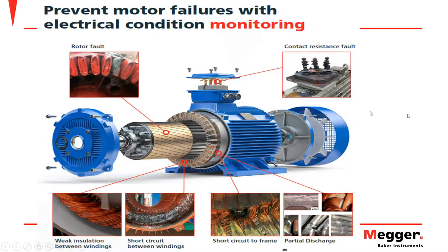Now, to prevent electrical failures, you can see here are some real issues that have led to motor failures. Some are just high resistance joints. Some are total burnouts. Some are just fusing to ground. Some are just a single phase that's burnt out, as opposed to a total burnout, for example. And the very left small window at the bottom there shows a little bit of arcing between some turns. Now, that is how these issues start: a little bit of arcing during startup. But then over a period of time of those startups, because of the AC condition of the startup current being positive, negative, it kind of carbonizes.